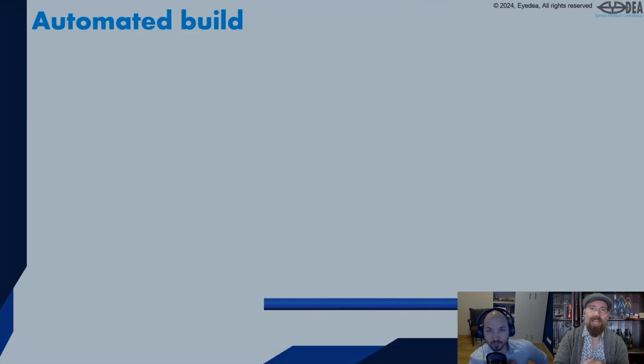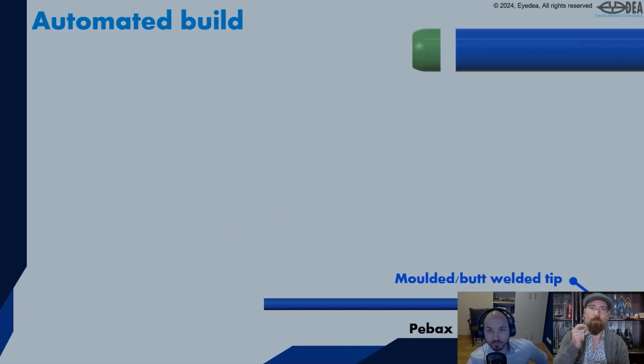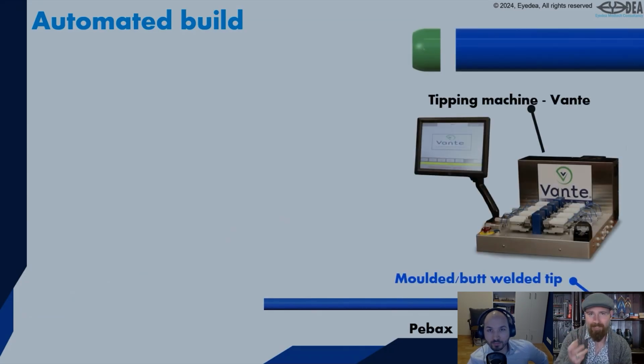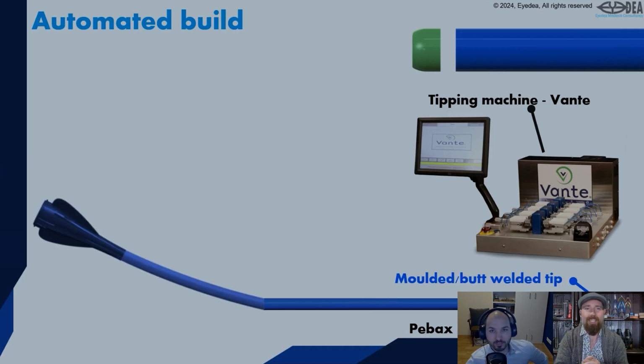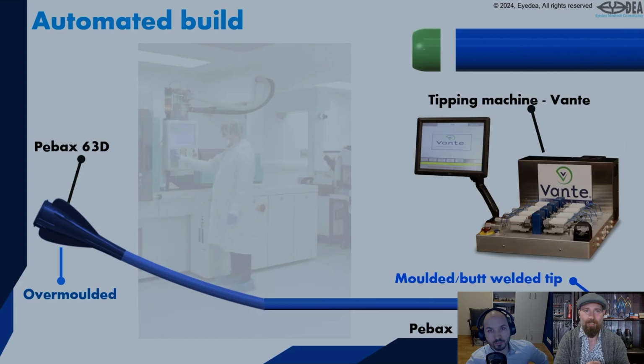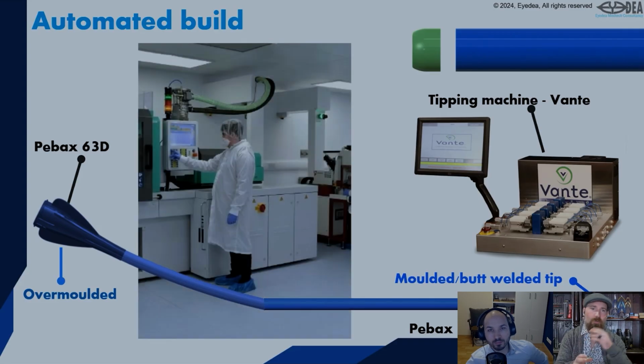And then ways that you can put it on, you can end up overmolding or butt welding on a tip. I'm not a big fan of this process, but I have seen some very innovative ways of melting on lower durometer polymers over the higher durometer polymer so that it's an overlap rather than a connected tip. And then same overmolding on with the proximal end, no glues, no adhesives, no holding them together and waiting for them to dry. And then your catheter shaft is done, and you can connect it on any of the bits at the end, whether it's the balloon or whatever other lumens you're trying to do.